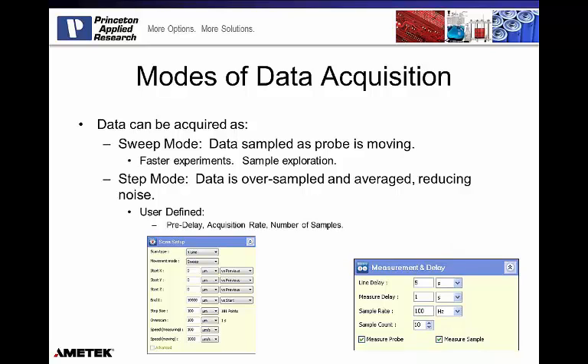While the mode of operation, feedback or generation collection, is really dictated by what you're trying to measure and the level of control you want to have in your system, the mode of data acquisition is simply this: in sweep mode, the data is sampled as the probe is moving. This is typically used for faster experiments or sample exploration. Then we'll go back and do a step mode test, where the probe moves to a fixed location, stops, and allows the user to oversample and average, thus reducing the noise in each pixel of the data map. In sweep mode, you define the sweep rate as a scan rate, in microns per second. In step mode, we define a pre-delay, an acquisition rate, and a number of samples. That oversampling and averaging reduces the noise in a single step, but it does increase the length of the experiment.